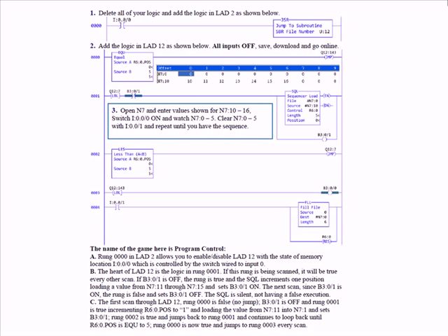So it will execute one execution of the instruction against these data locations. But it will also set B301 to the on state, or to 1, which means that this rung will be false the next time through, because if you look at the permissive, B31 had to be off for this rung to be true. But now we're turning this bit on.